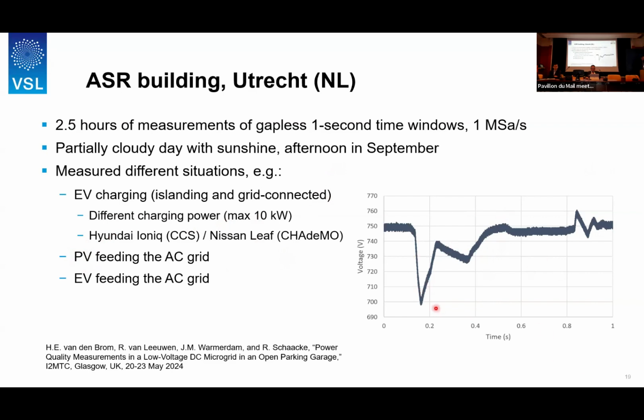The example of the waveform here is when the EV charging was started. So as soon as it started, the voltage dropped by 50 volt or so. This is apparently a very small grid with a very low inertia, which is to be expected for such a small grid.